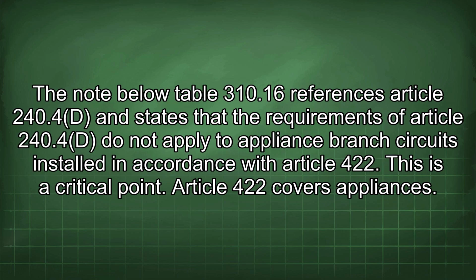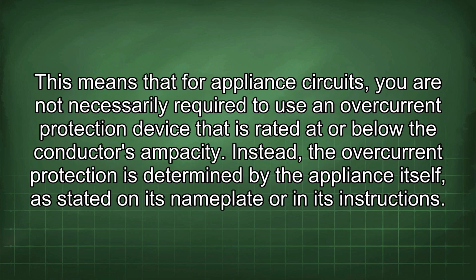The note below Table 310.16 references Article 240.4d and states that the requirements of Article 240.4d do not apply to appliance branch circuits installed in accordance with Article 422. This is a critical point. Article 422 covers appliances. This means that for appliance circuits, you are not necessarily required to use an overcurrent protection device that is rated at or below the conductor's ampacity. Instead, the overcurrent protection is determined by the appliance itself, as stated on its nameplate or in its instructions.